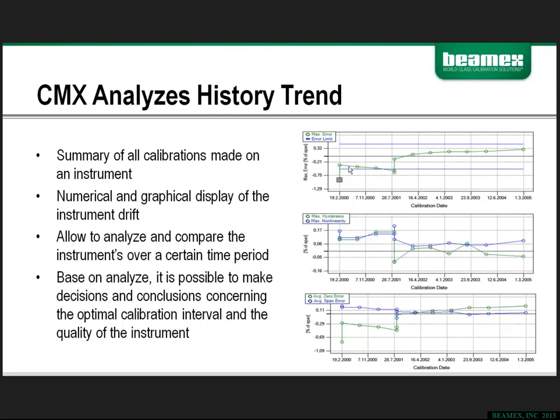So you can see it was in tolerance in its first calibration, and as it followed on, it tended to drift to where, at such a point, it was actually out of tolerance just after the July calibration. And at that point, it was adjusted to be brought back into tolerance. So that's going to be representative of before and after data, with the top line being after data, and then it drifted in the other direction after that. And that's very common with particular instruments. If they drift in a particular direction and then are adjusted, a lot of times that drift will reverse itself and go in the other direction. So over time, you can see how a particular instrument has performed and whether or not it would be justifiable to replace that instrument or optimize it.